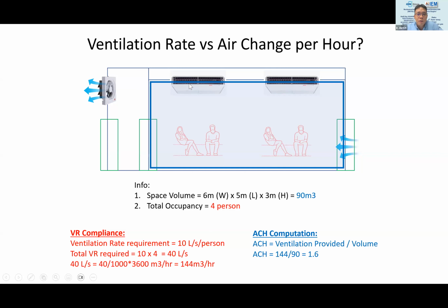So if you have a space of 6 meters by 5 meters by 3 meters, you will have 90 cubic meters. One air change means 90 cubic meters per hour. 12 air changes means 90 cubic meters times 12 per hour. Let's say you have four persons, and the requirement is 10 liters per second per person. That's how you come out with 10 times 4 equals 40 liters per second. Then you have a conversion: 40 liters per second is actually 144 cubic meters per hour. If you compute based on air change per hour, then 144 cubic meters per hour divided by the space volume means the fresh air you are providing is actually 1.6 air changes per hour.